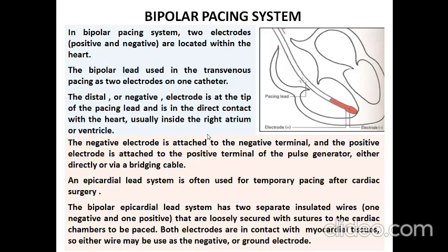An epicardial lead system is often used for temporary pacing after cardiac surgery. The bipolar epicardial lead system has two separate insulated wires that are loosely secured with sutures to the cardiac chambers to be paced. Both electrodes are in contact with myocardial tissue, so either wire may be used as the negative or ground electrode. So this is regarding the bipolar pacing system.